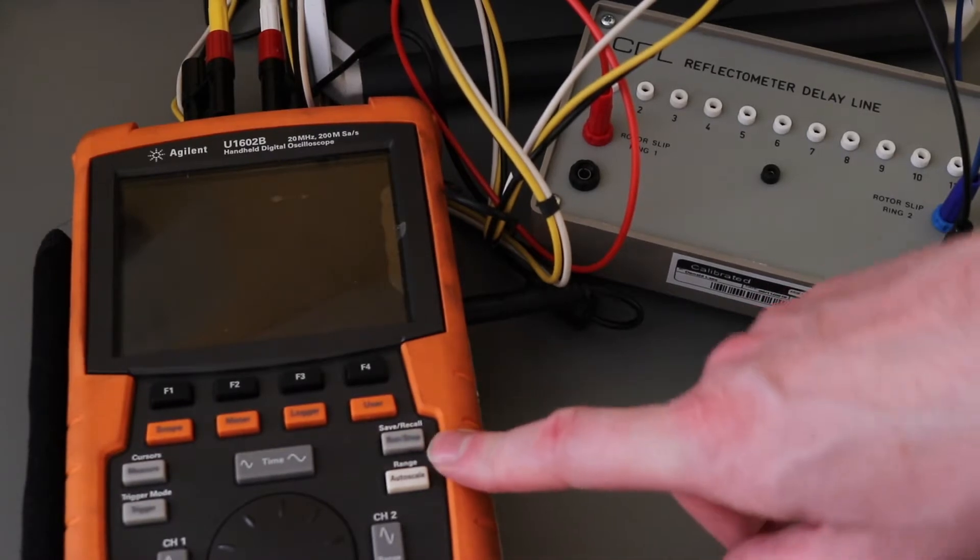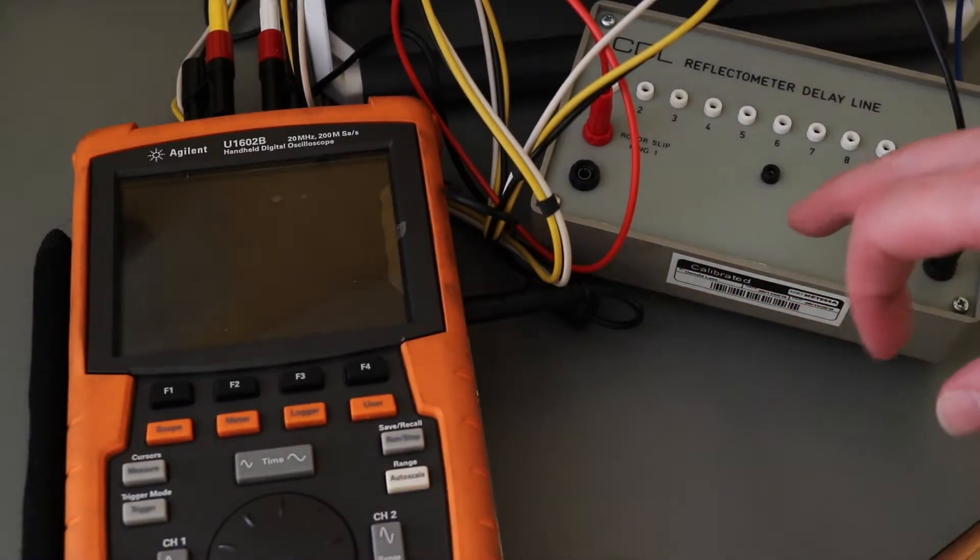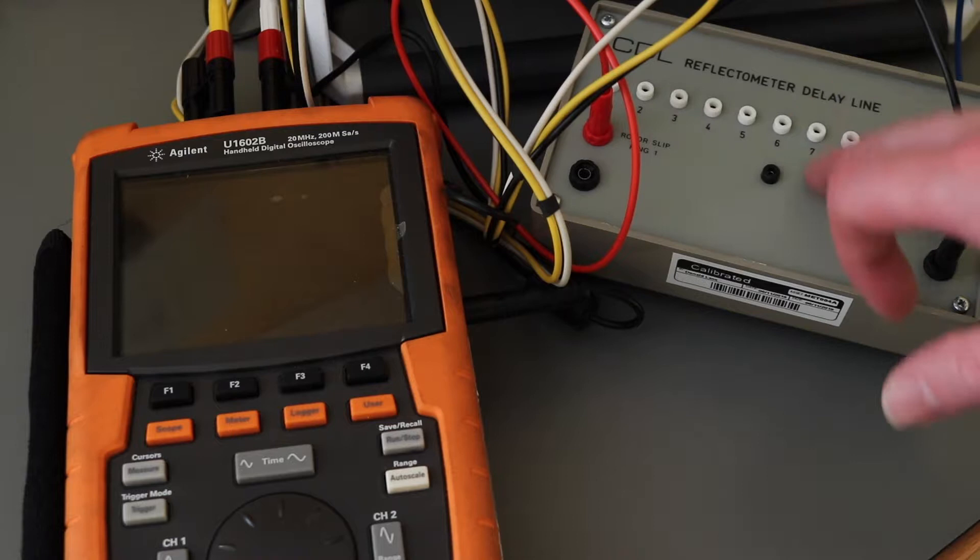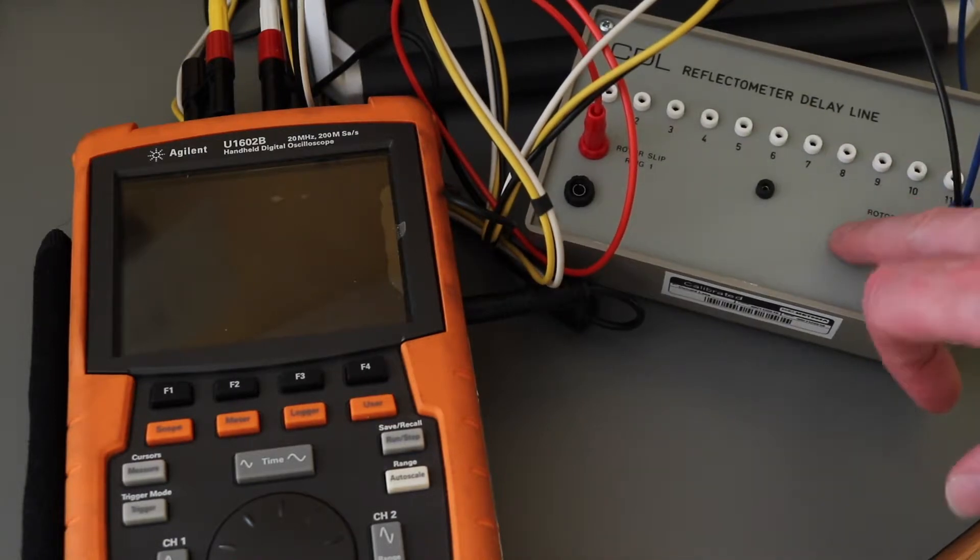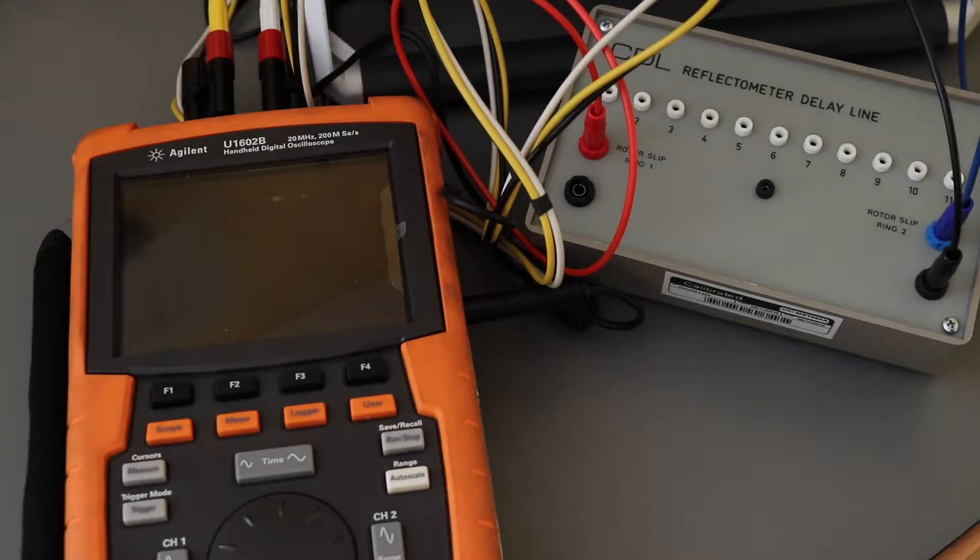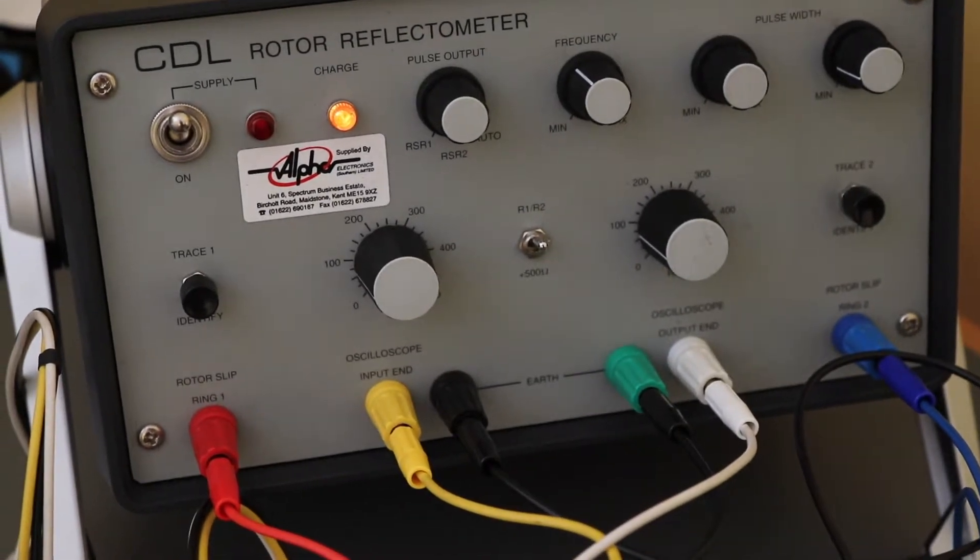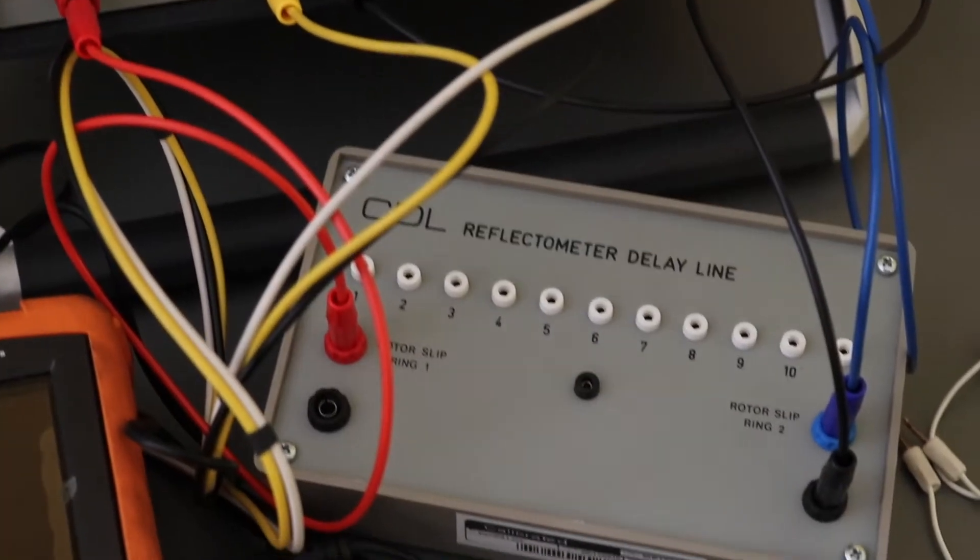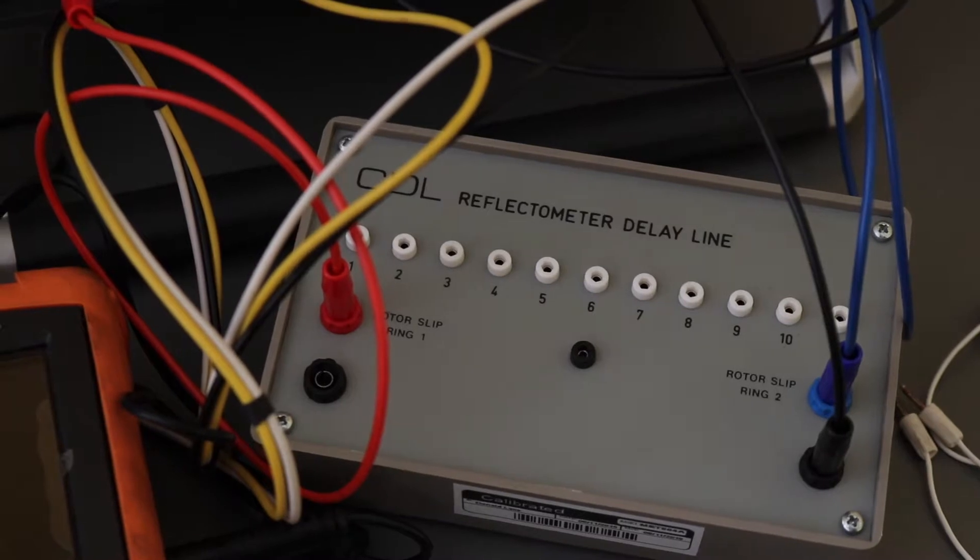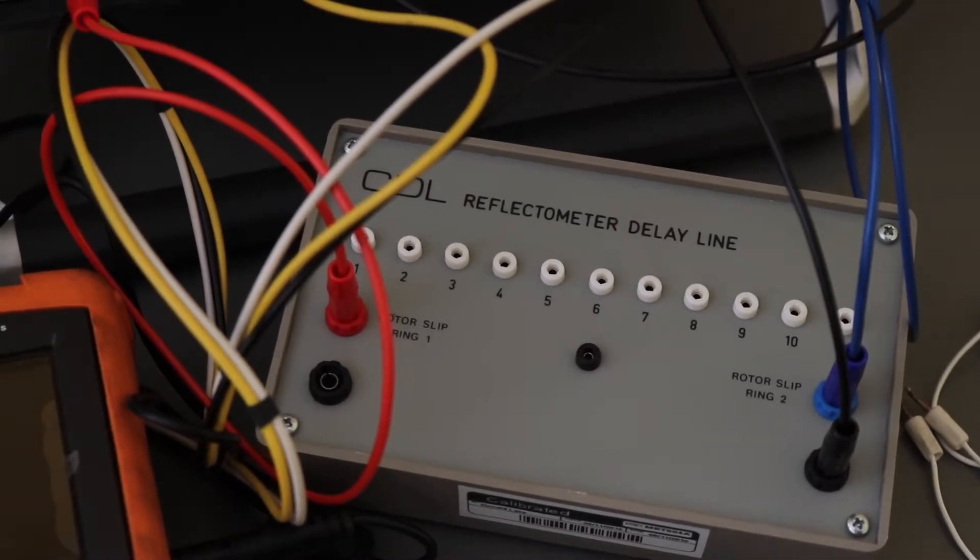Demo of the U1602B DSO. I'm using a rotor reflectometer which is used on generator rotor windings and sends a signal down to see if there's any inter-turn faults. There's the rotor reflectometer, that unit there is a little simulator that I'll use to create the signals.